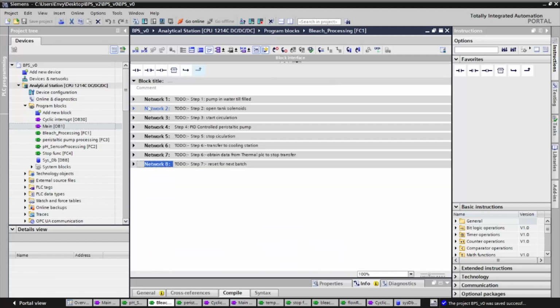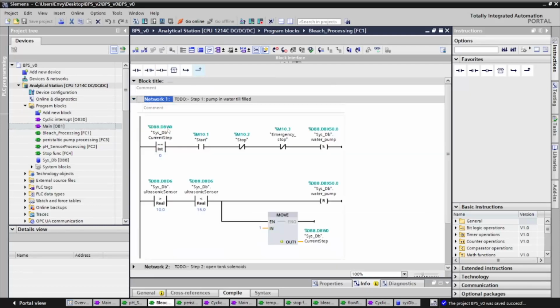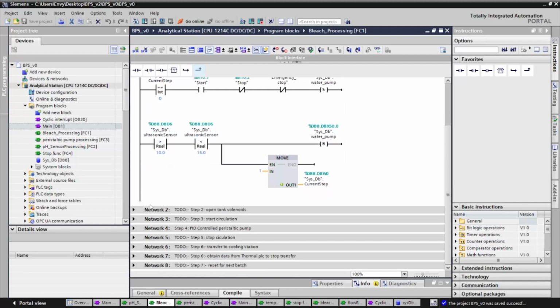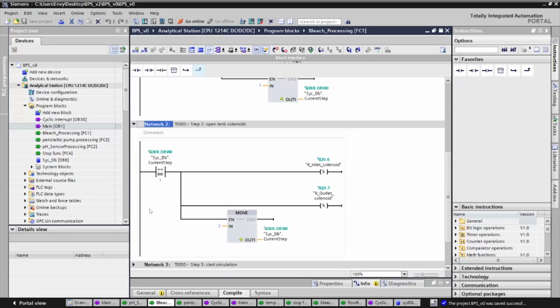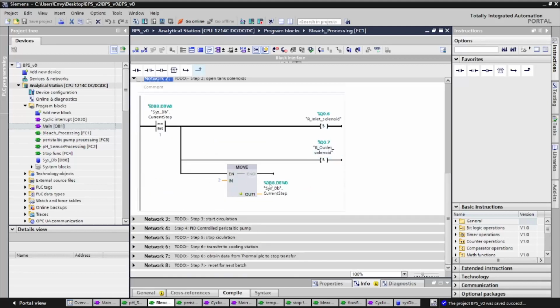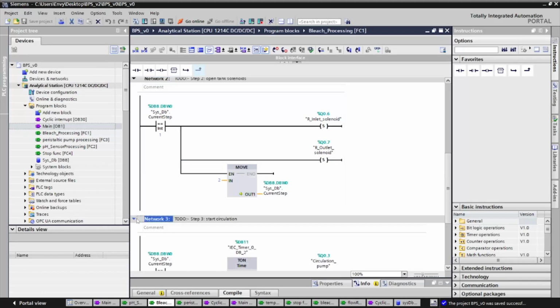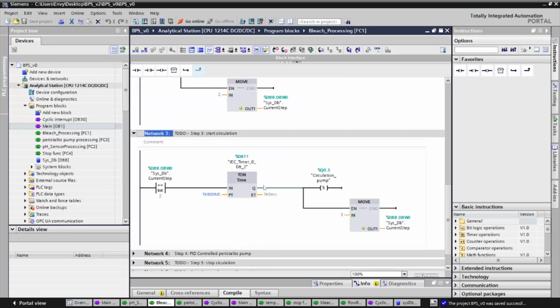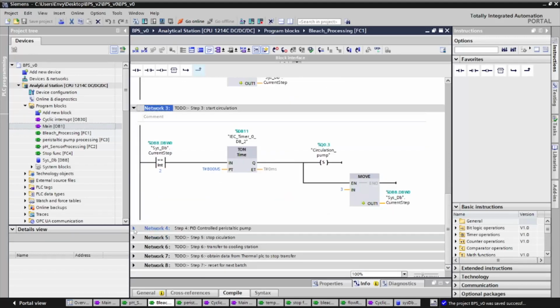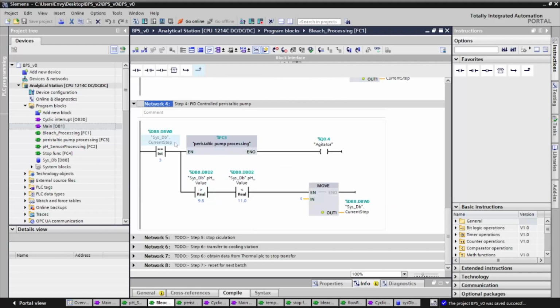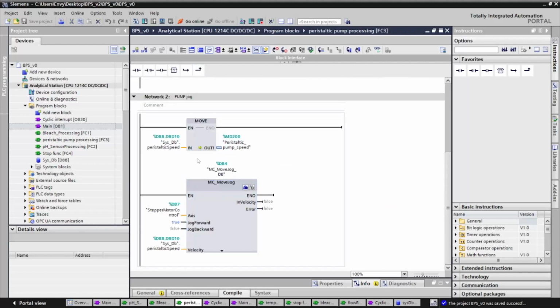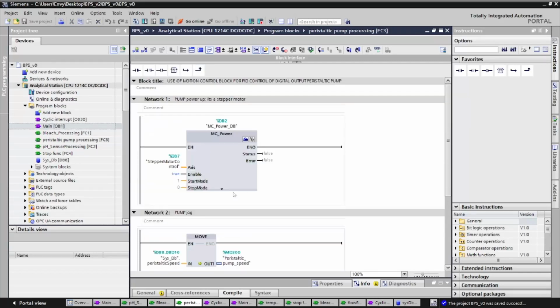It starts with the first network, where we pump in the distilled water and monitor its level. On the next sequence, we open the inlet and outlet solenoid of the reactor tank, which we have filled with the water, and turn on the circulation pump to circulate the distilled water. At that time, we call the peristaltic pump, whose speed we are controlling with a PID we implemented.